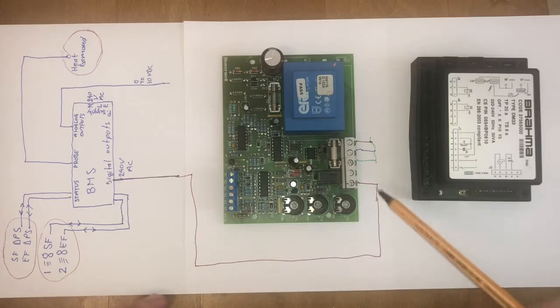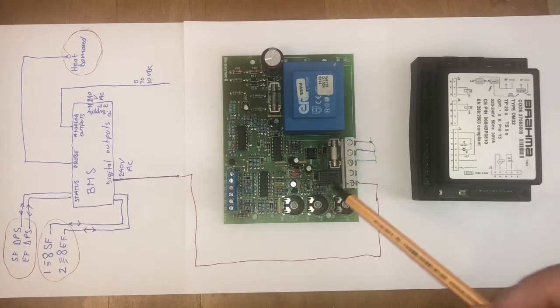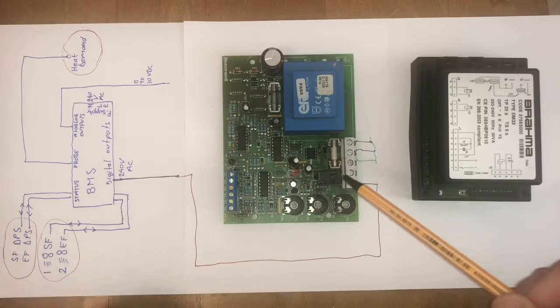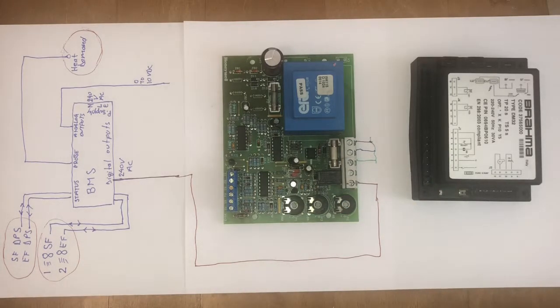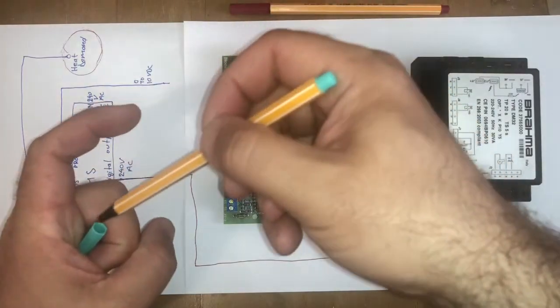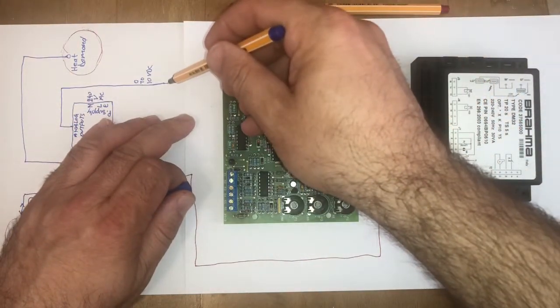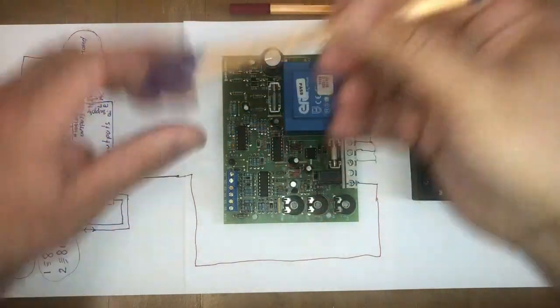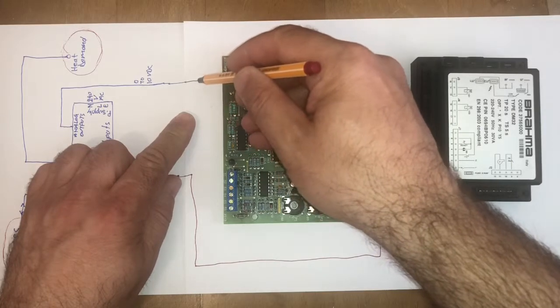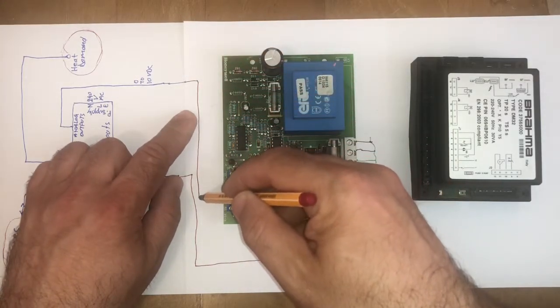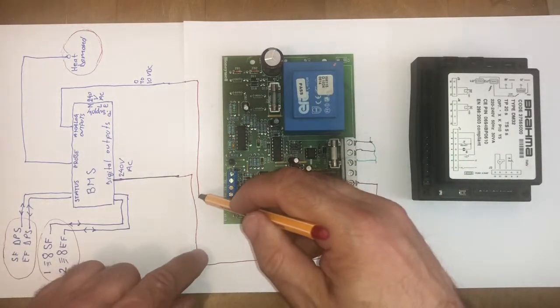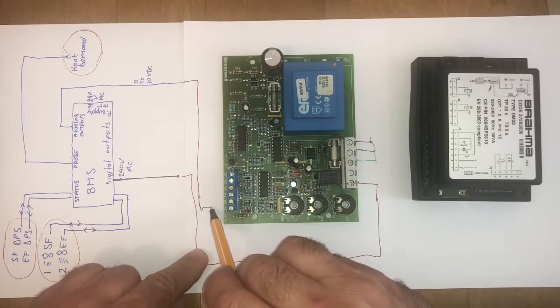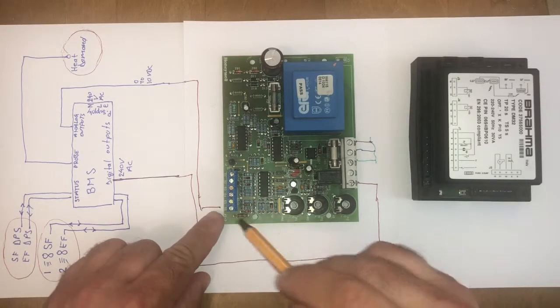Now the building management control will send the power to this relay. This relay is an open circuit now, because it is not enabled. It is on standby mode. Then, because you have a heat demand, what you're going to do, and I'm going to use the red pen as well, you go with a signal. Just have to do it with red, and let's assume we have two cables here, plus and minus, and they carry 10 volts. So you'll come with this 10 volts, and you'll go with minus to 66, which is the last screw here.